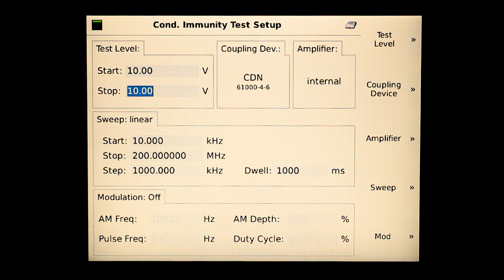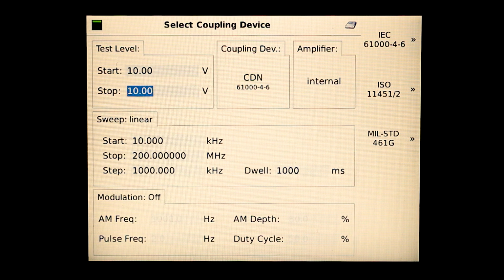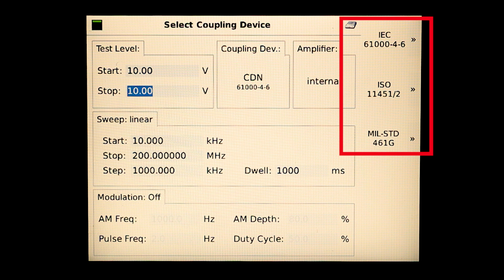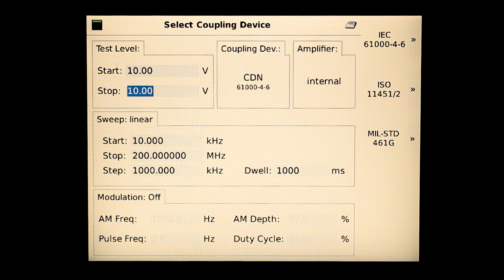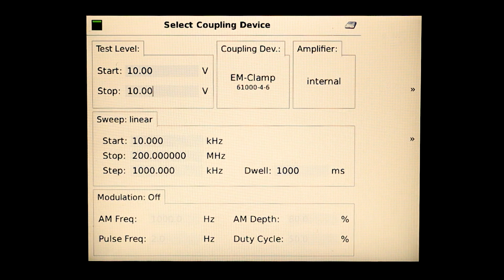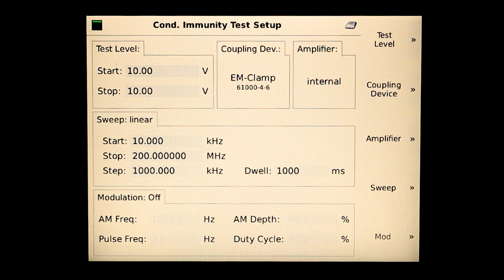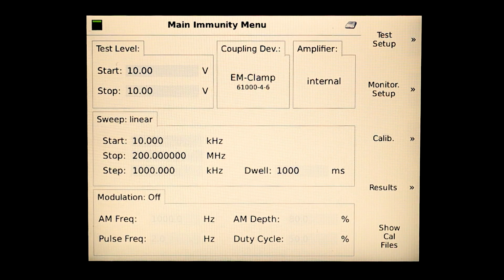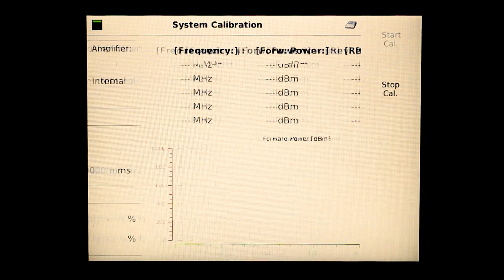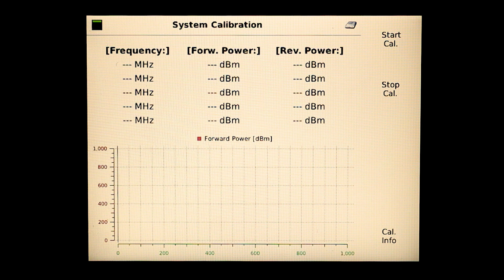Let's click the coupling device. And you can see right here, there's a list of different standards. We have IEC 61000-4-6, ISO 11451 and 11452, as well as MIL standard 461. Let's click the IEC requirement for today's video. And let's change that from CDN to EM clamp. And then we're not going to use a probe. Let's hit back now. All right, so let's go back one more. And then when you're ready, we're back to our main immunity menu page. You can see the third option down right there, we have calibration, so let's select that. And then you go to system calibration and then hit the upper right for start calibration.